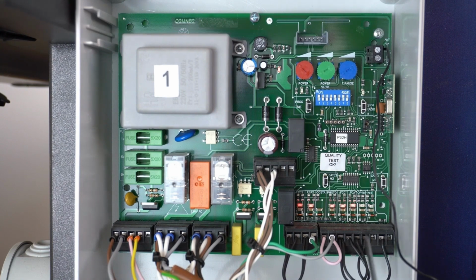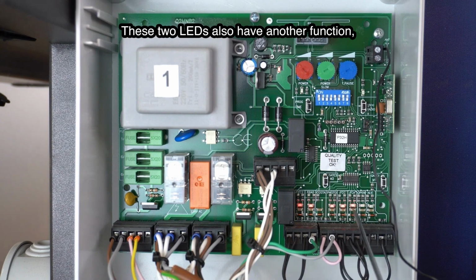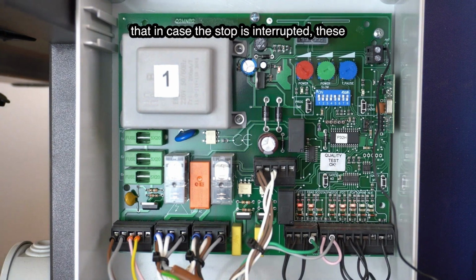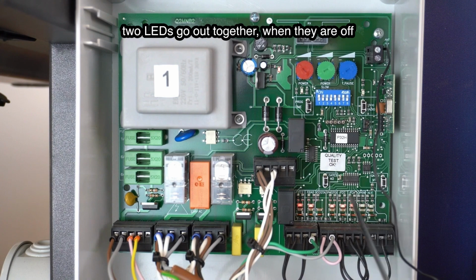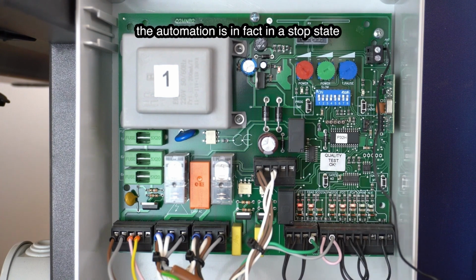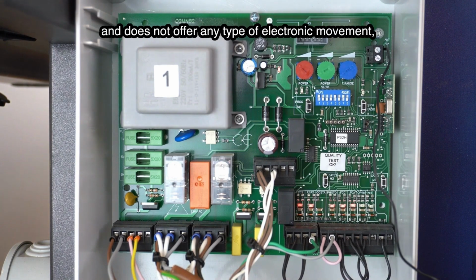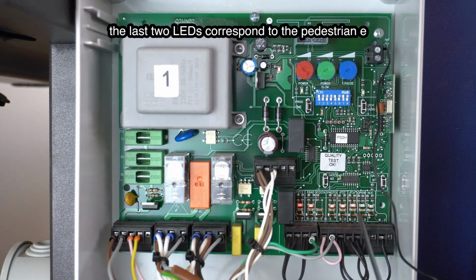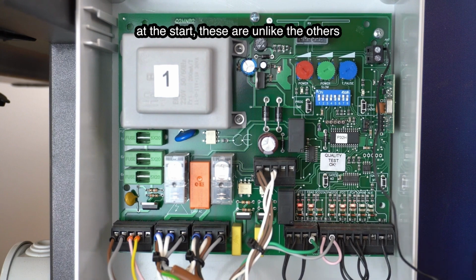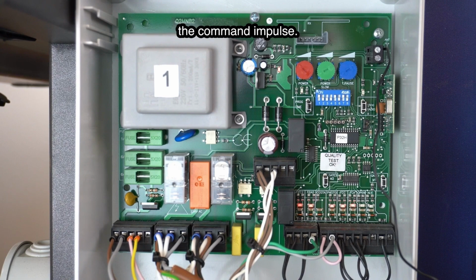These 2 LEDs have a function that in the event that the stop is interrupted, these 2 LEDs turn off. When off, the automation is in stop state and does not offer electronic movement. The last 2 LEDs match pedestrian and start. Unlike the others, they are always off and turn on only when they receive the control impulse.